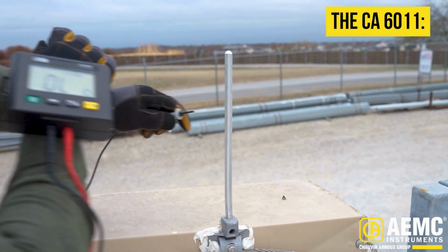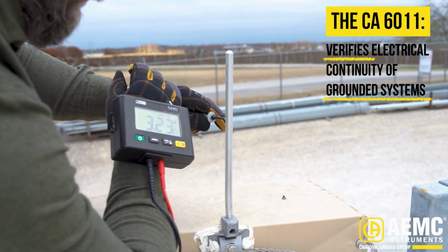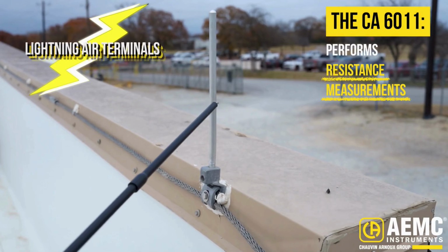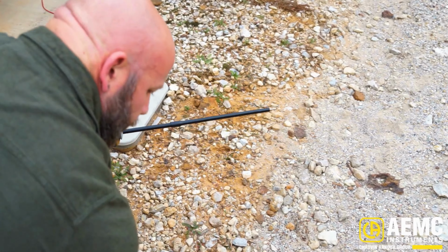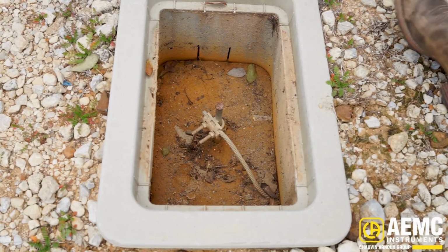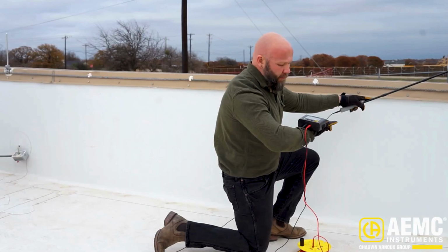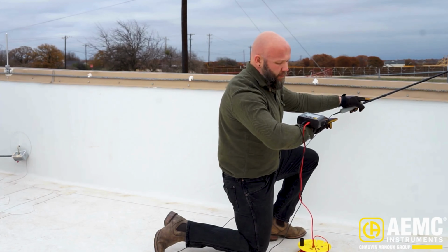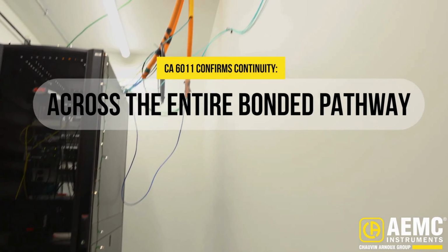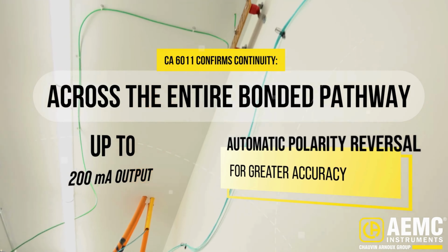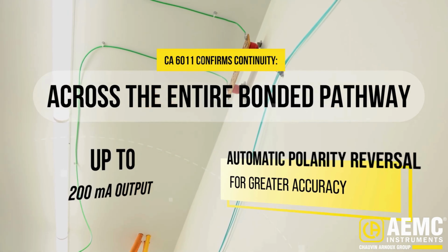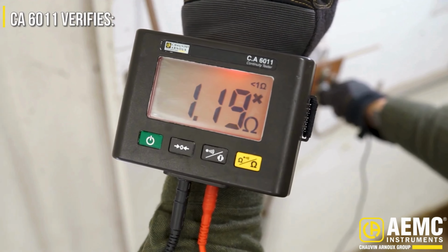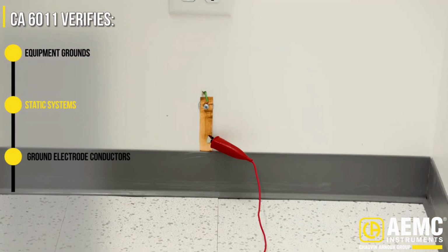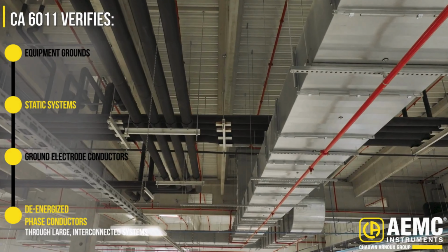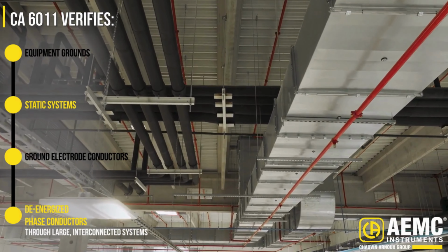The 6011 is designed to verify electrical continuity of grounded systems and perform resistance measurements on systems like lightning air terminals that rely on solid bonding back to Earth. You can quickly verify that a low resistance conductive path exists from the air terminal through the lightning protection system by connecting to a known ground point and testing along the conductor. The CA6011 confirms continuity across the entire bonded pathway using up to 200 mA output, with automatic polarity reversal for greater accuracy. It's also ideal for verifying a conductive path on equipment grounds, static systems, ground electrode conductors, and even continuity on de-energized phase conductors throughout large interconnected systems.